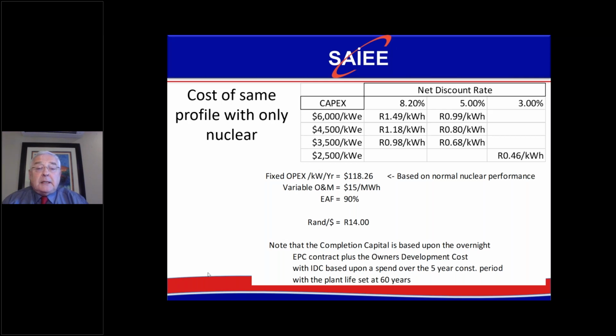What you can see is this: if you take $6,000 a kilowatt, which is an expensive nuclear station, at 8.2% discount rate, you get 1.49 rand per kilowatt hour. So clearly nuclear does not make sense. Even at $4,500 a kilowatt at 8.2%, it doesn't make sense. At $3,500, it starts making sense.